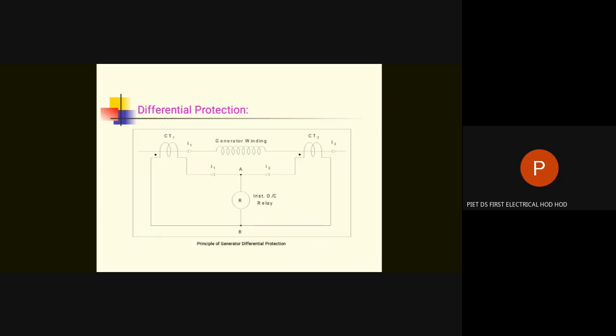Now, how can the insulation between R and Y fail? If R and Y insulation fails, then there will be an RY fault. If the insulation between Y and B fails, then there will be a YB fault. Now, the generator design is such that two different conductors of different phases are never kept in a single slot. Therefore, an RY or YB fault in a generator slot is not possible. But that is possible in the overhang portion.